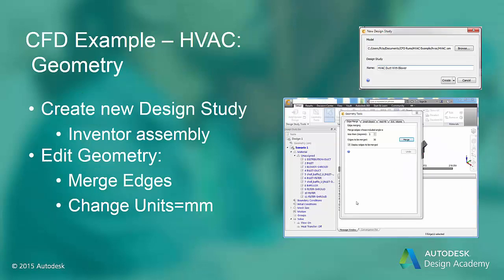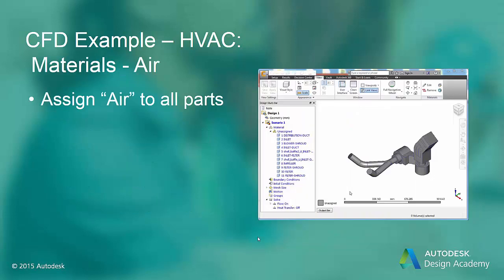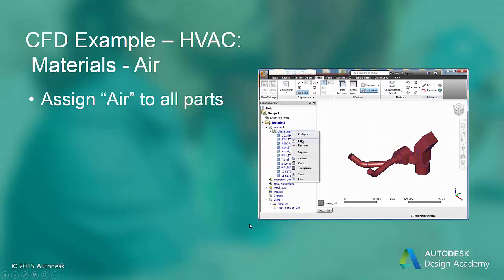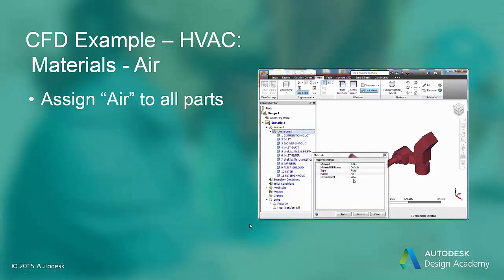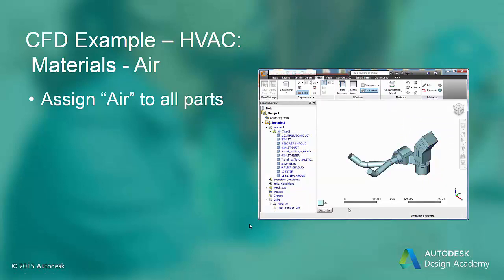An Inventor assembly named HVAC.IAM has already been created. As in previous CFD simulations, we will merge the small edges in this model and use the millimeter system of units. Since most of the parts in the HVAC assembly are air parts, we begin by assigning air to every part in the assembly model. One important note about distributed resistance macro models is that they need to be surrounded by air or fluid parts in order for the software to recognize them.